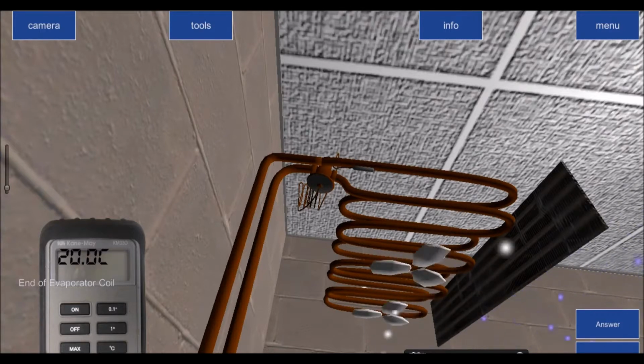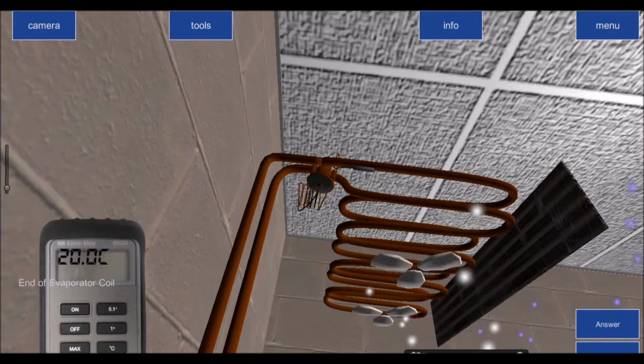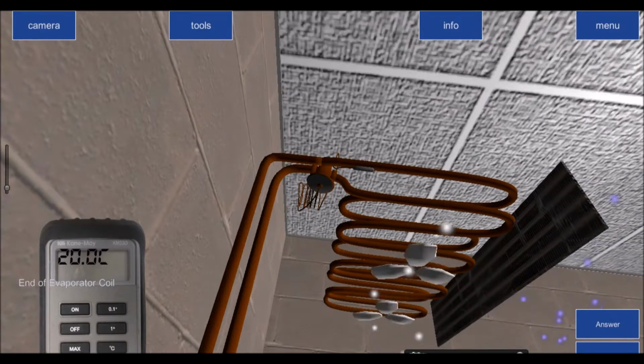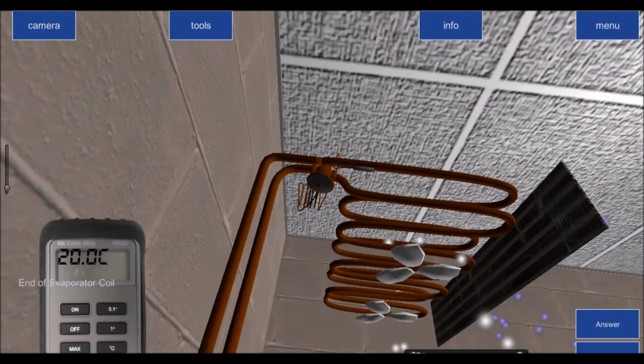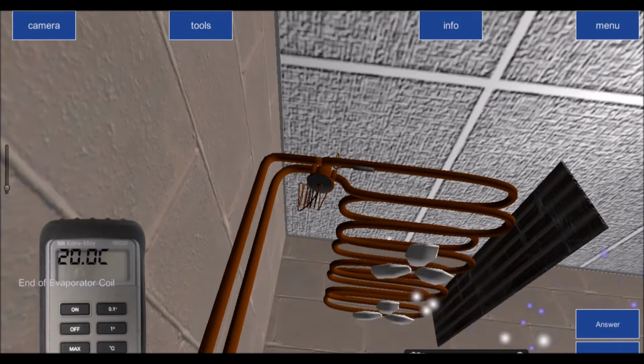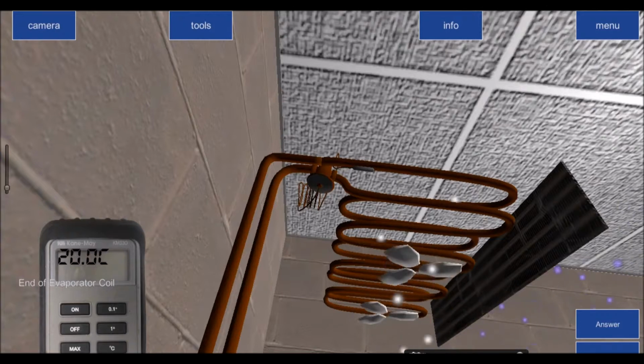And the difference between the temperature at the inlet of my evaporator and the temperature at the outlet of my evaporator is my superheat value. So we have to remember that superheat comes as a value. It doesn't come as an actual temperature. We're not worried about it as a temperature, or we don't think of it in terms of a temperature. We think of it in terms of a value.